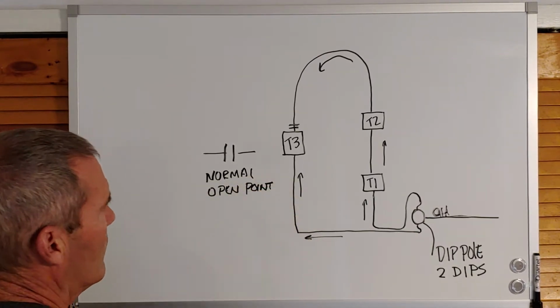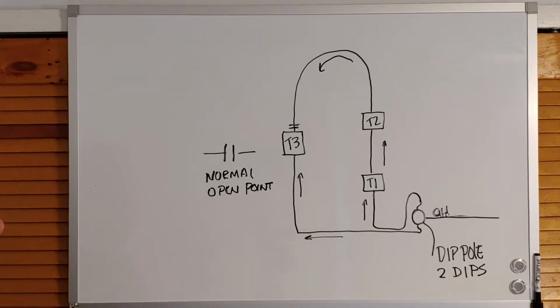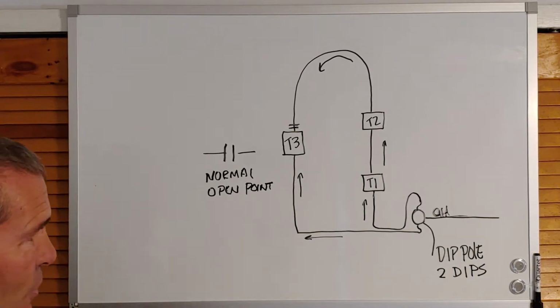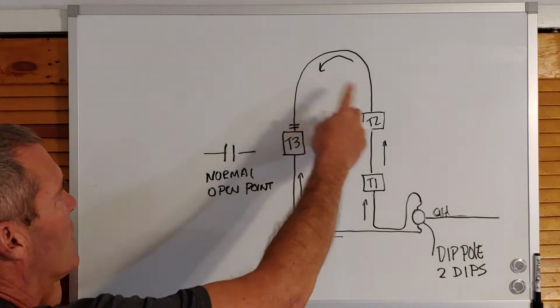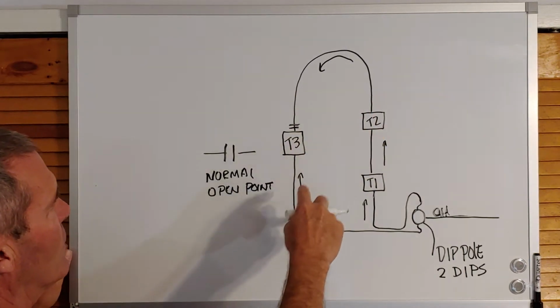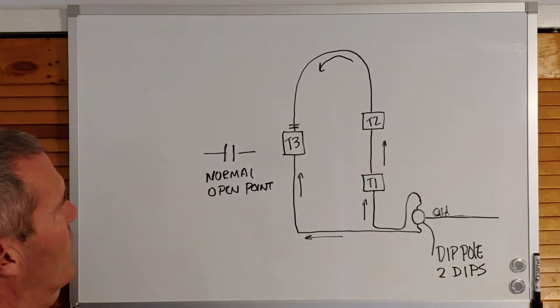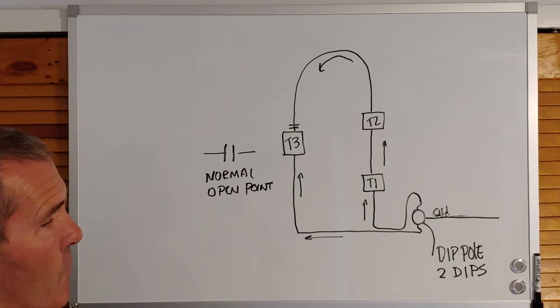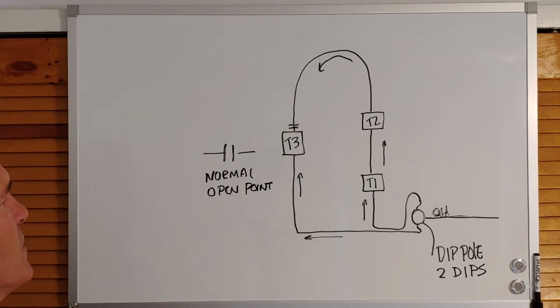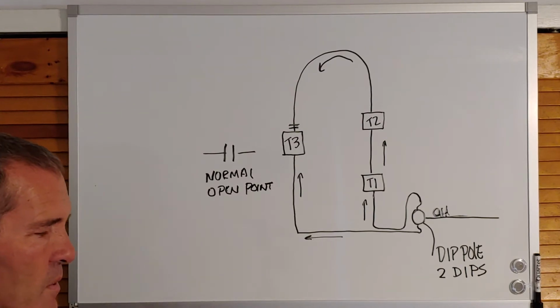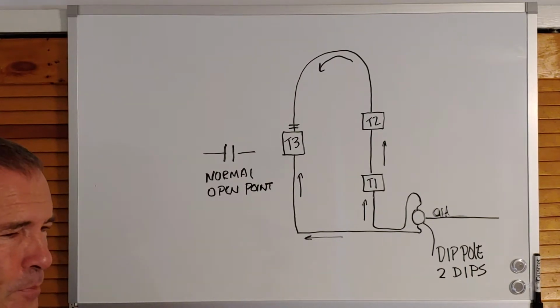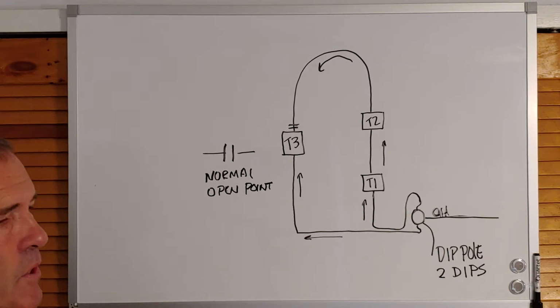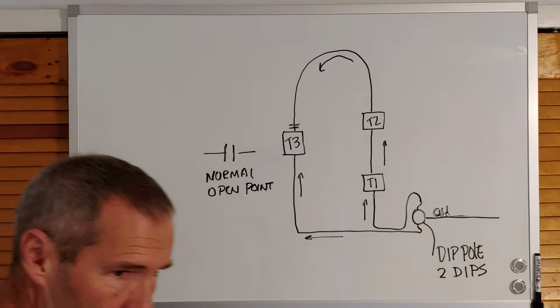Remember, in loop-fed systems we don't have it looped all the time. It doesn't stay looped, we have the capability to loop. That's why we have to have an open point in this situation, and we have an open point in all loop systems to be able to backfeed. So that's a good question: in a loop system, underground system, do you have to have an open point? The answer is yes.